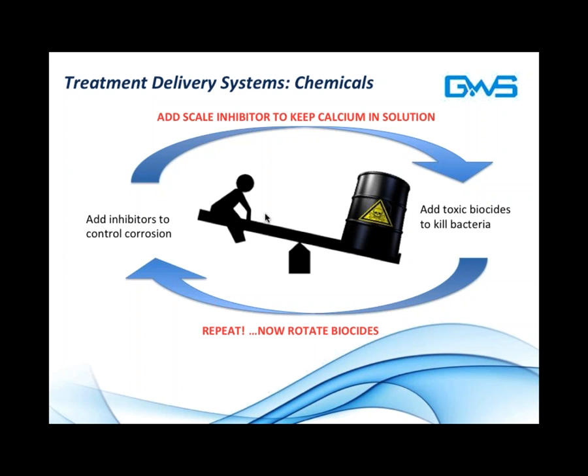This is like chasing a target, like the carrot in front of the rabbit, always running to catch up with the system as load changes or as demands change within the system. On top of this, keeping cycles of concentration low to avoid scale is in the best interest of the service partner, because if you have to cycle the water higher, the risk of scale is greater, and that's a problem for the service partner if the scale forms.